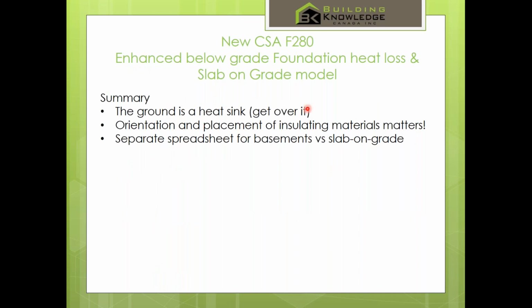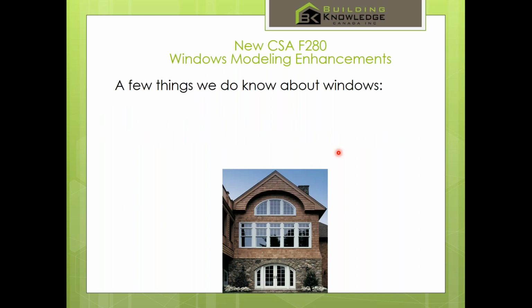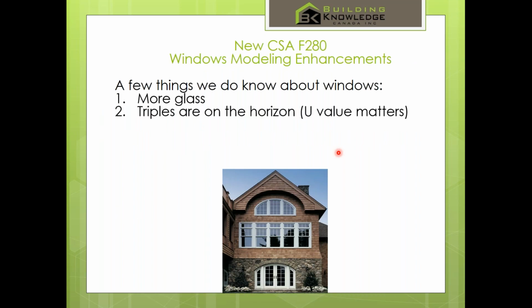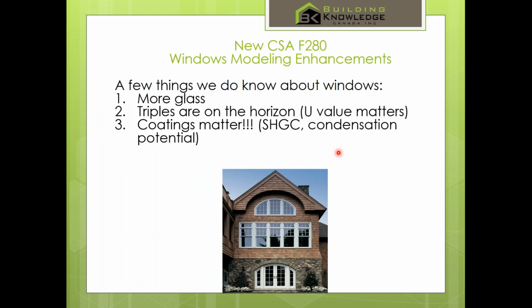So number one is we know the ground is a heat sink, so get over it. We're going to have to account for the heat that's lost. Orientation of the insulation, outside, inside, above the slab, below the slab does matter. There's two different spreadsheets, one for slab on grade and one for basements. Windows, a few things that we do know is we're getting a lot more glass. Triples are coming very quickly in a lot of zones. U-value does matter. Coatings matter a lot. Solar heat gain number is incredibly important, and we can't ignore this thing called condensation potential.